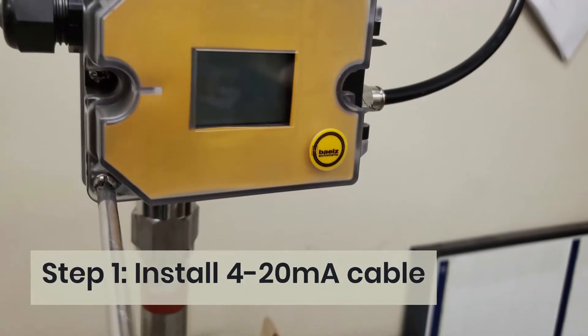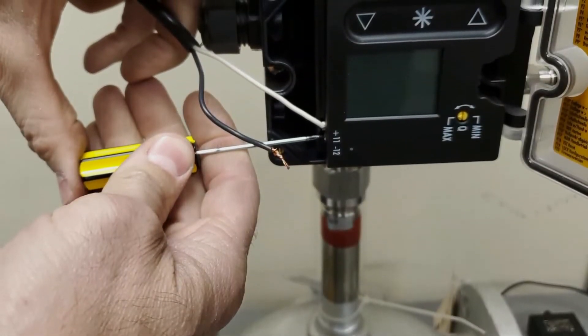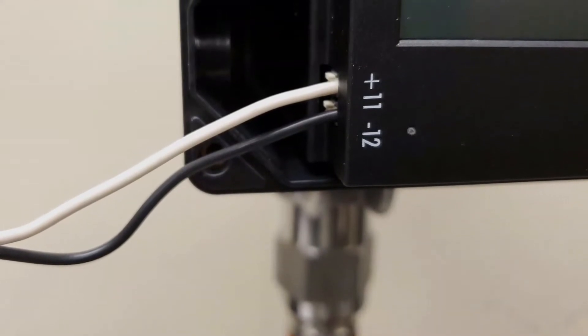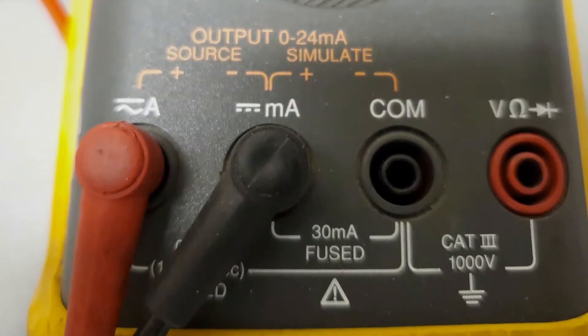Step 1: Install 4-20mA cable. Unscrew the cover. The white wire goes on terminal plus 11, the black wire goes on terminal minus 12. Connect the 4-20mA cable to the meter leads. Insert meter leads to source on the Fluke process meter. Turn the dial on the meter to mA output.